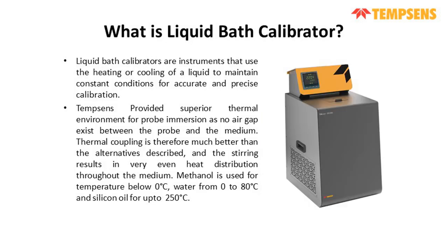Now moving on to the liquid bath calibrators. Till now we have completed the dry block segment, and now we move to liquid bath calibration. Liquid bath calibrators are instruments that use the heating or cooling of a liquid to maintain constant conditions for accurate and precise calibration. We use three mediums: methanol, silicon oil, and water. Methanol is used for temperatures below 0 degrees, then we have water from 0 to 80 degrees, and then we have silicon oil up to 250 degrees centigrade.